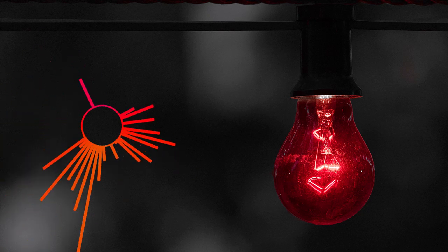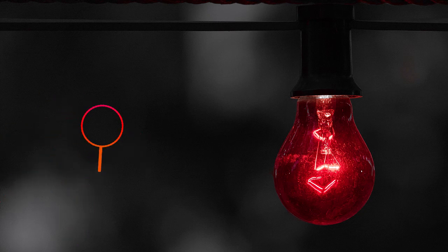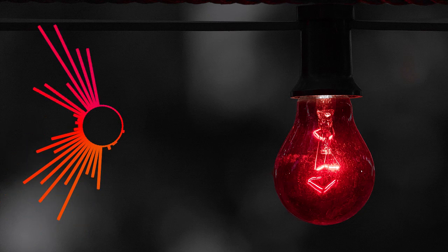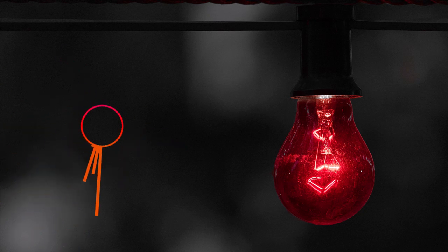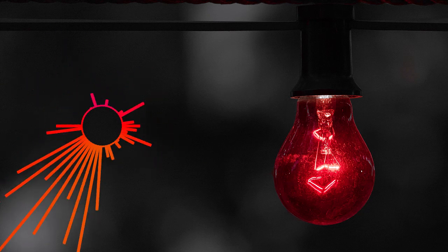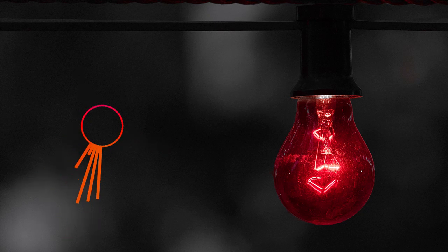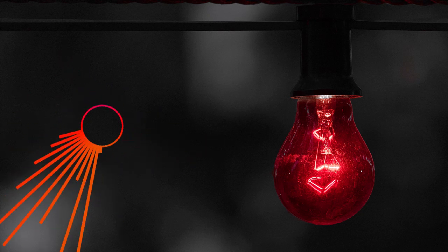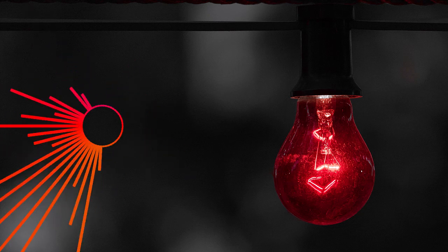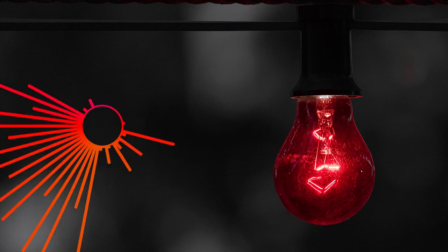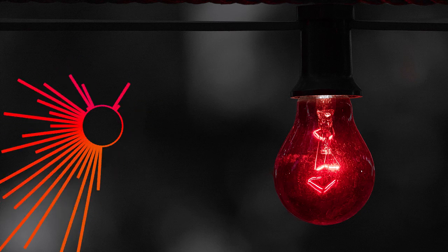So now let's talk about the lighting circuit and where all the power comes from. All the parts that we have talked about, lamp, ballast, luminaire, and control, are all connected through something called the lighting circuit. A lighting circuit is the wiring that brings electrical power to your lighting system. Depending on how much electricity the circuit can safely carry, or the amp rating, and how much each luminaire uses, the watts, you can connect multiple luminaires to a single circuit. Understanding load capacity is very important when installing or upgrading lighting. If the load is too high for the circuit, you could blow a breaker or even start a fire.